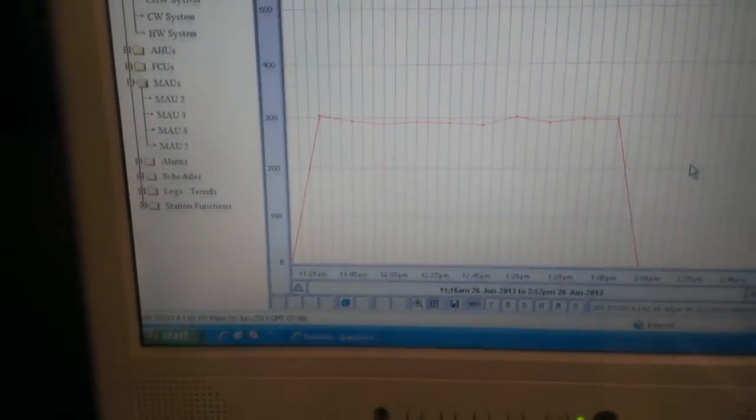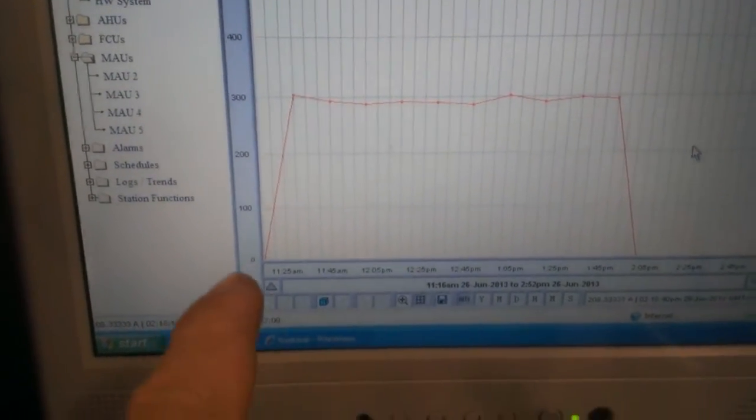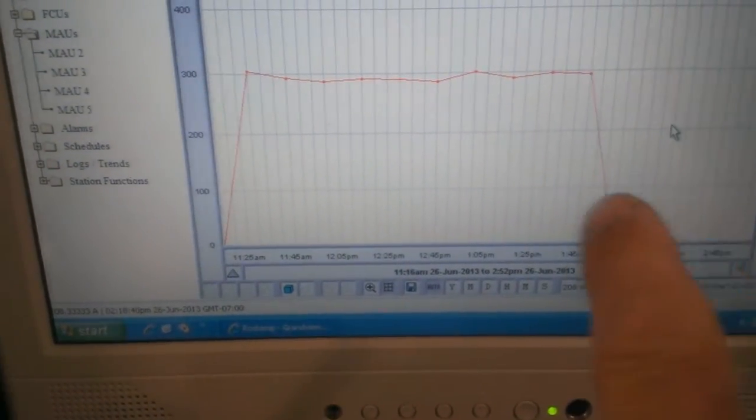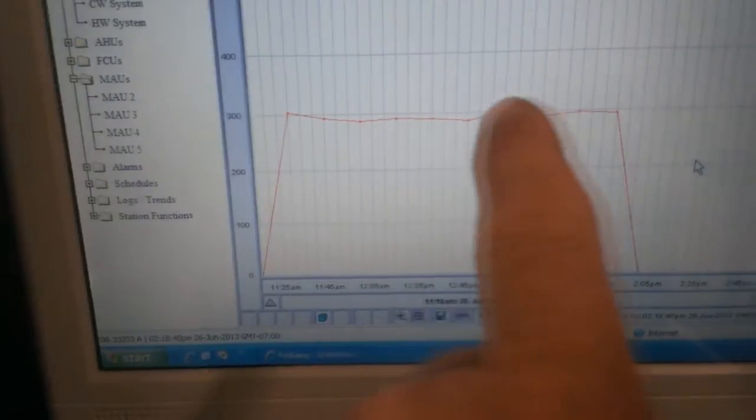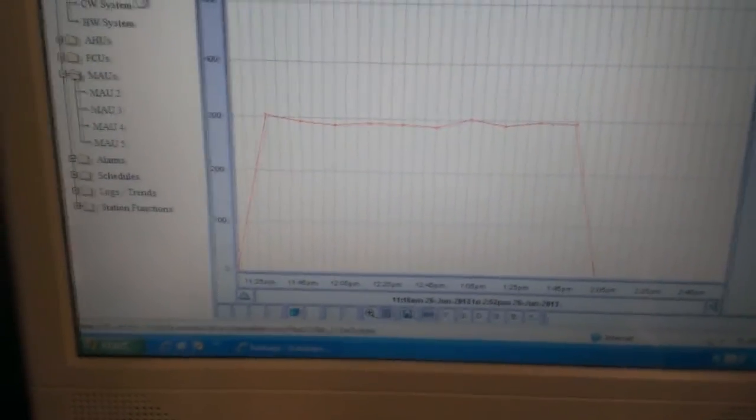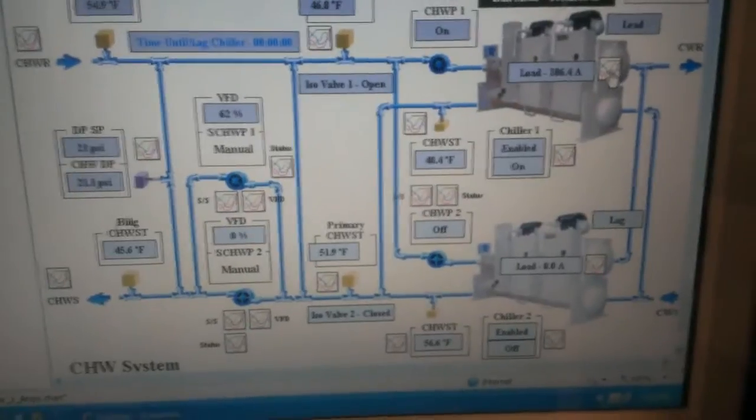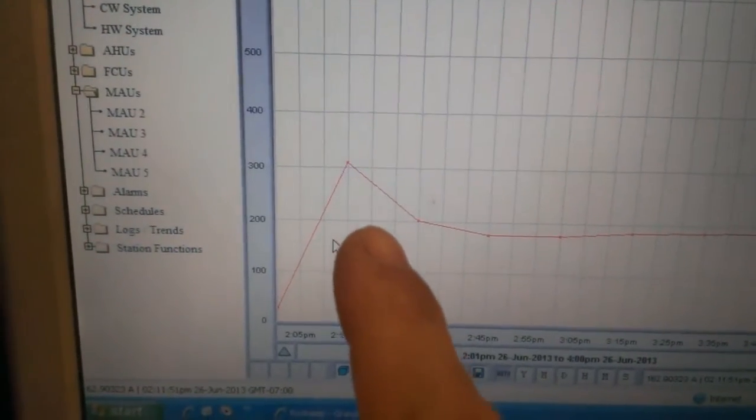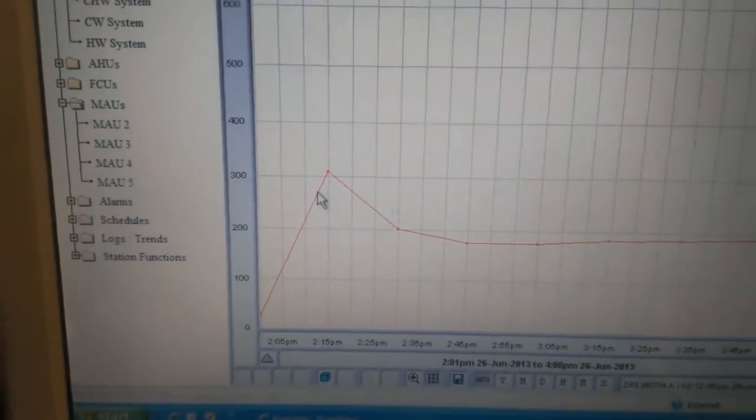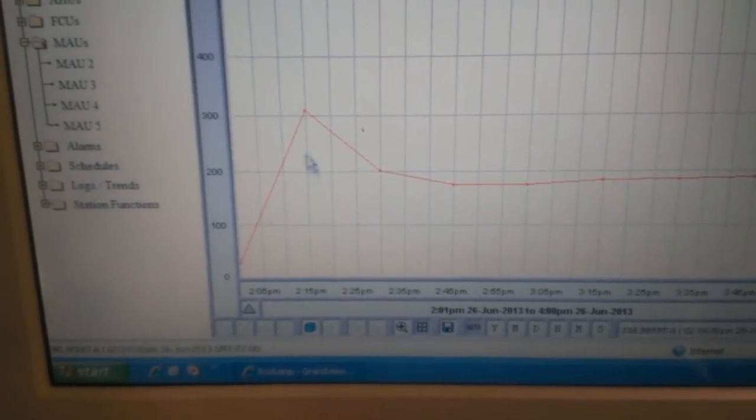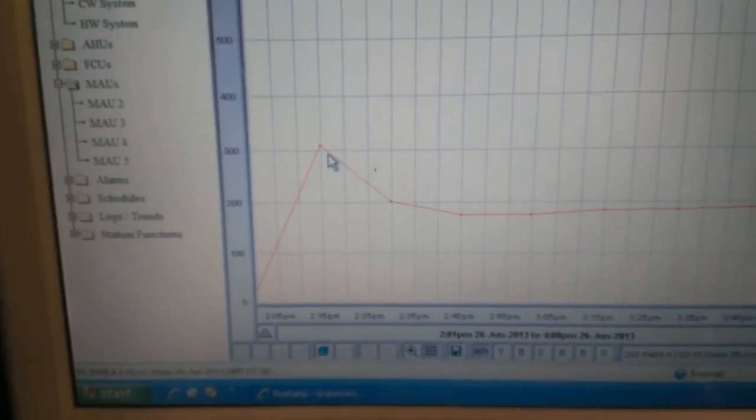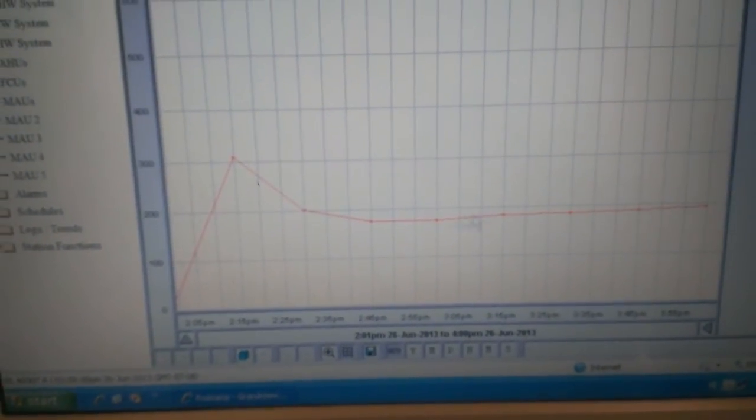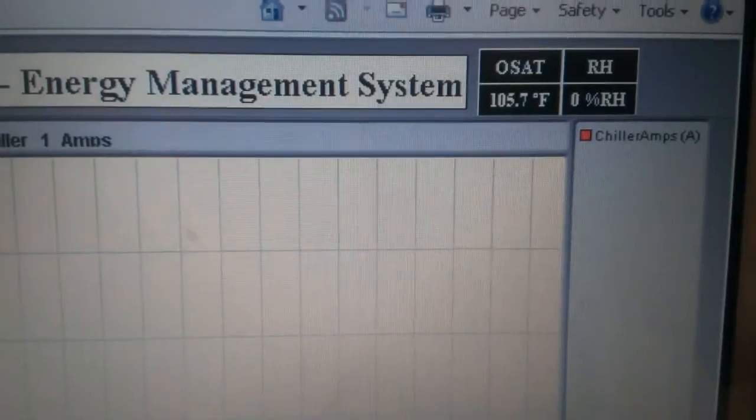Okay. Got enough of a log now. The centrifugal chiller, when I had it online while I was working on the other one, was running from about 11:30 until about 2. And started out at over 300 amps and stayed right around 290 the whole time. And that was with just to maintain temp the whole time. Now, if we look at the log on the triple-screw with the VFD on it. Okay. It kicked back in. It kicked in about 2:15. It was a little over 300 amps. But the load was really high because the building got warm while it was off like 10 minutes in between switching it over. But then it, as it caught up, now it just kind of hovered around 200, down to 190 or so.